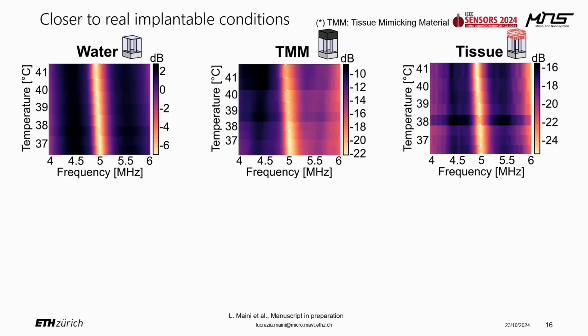Here I performed 3 different experiments. On the left side, I have again the water characterization, the calibration for our sensor. In the middle, we have some results with TMM, which are tissue mimicking materials or phantoms. These are materials that you can build in the lab with agar and graphite. And the advantage of these materials is that you can control the attenuation coefficient of these phantoms, and they do not degrade so fast over time, such as in the case of tissue. And on the right side, these are the results for animal tissue.